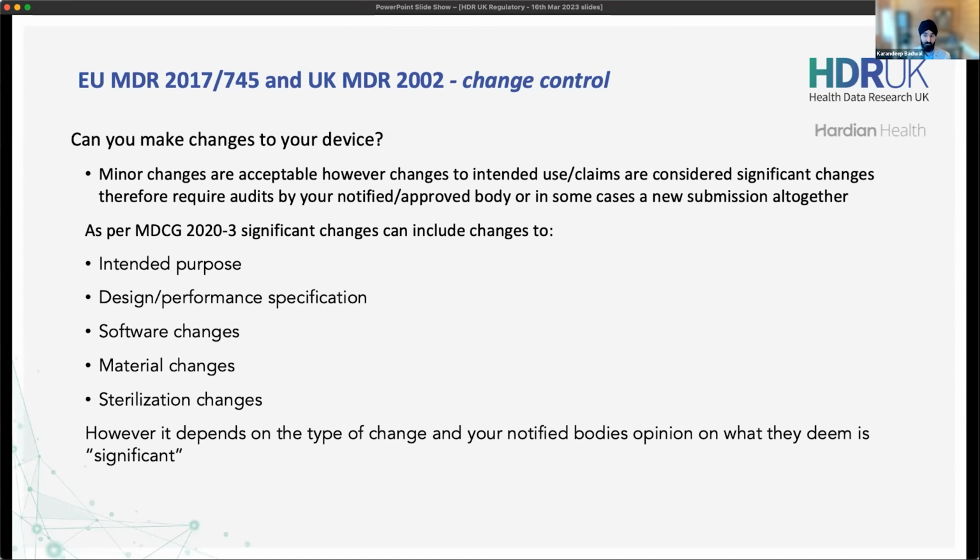And then the notified body has two choices. They audit what they think is affected, or they turn around and say to you, you have to have a new submission altogether because you changed it so much to the point where it's basically a different device.